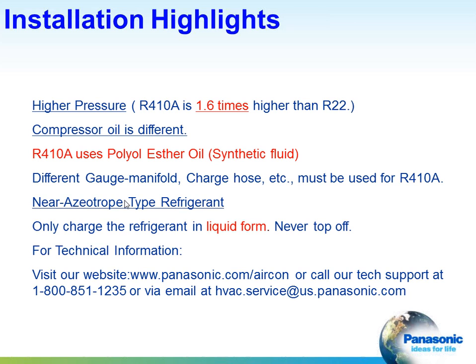All right, I think we're all familiar with R410A at this point. It's a higher pressure refrigerant, about 1.6 times higher than R22. The compressor oil is different. Do not use existing line sets unless they're properly cleaned, and I would say steer away from that in any case. Conventional systems, if you're replacing an existing ducted system and it's an R410A system, and the line sizing is proper, then you can do that.